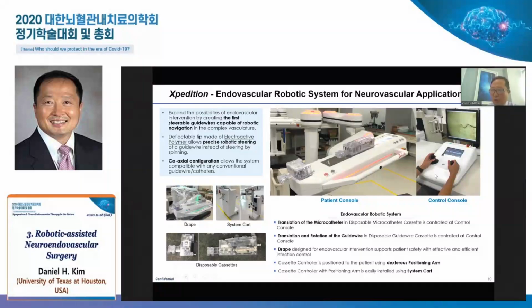The surgeon or interventionalist sits at a console and has joysticks: the left for the microcatheter control for translation and rotation, and a right controller for rotation and translation of the micro guide wire. Not only that, it's got a push button, and inside it's got a touch screen to control millimeter or sub-millimeter translation and rotation as well. That will give you the micro control that you're looking for on a delicate anatomy. With the steerable guide wire tip at the front and the micro control capability at the console, it can give you all the micro control that you're looking for. So it's a coaxial configuration.